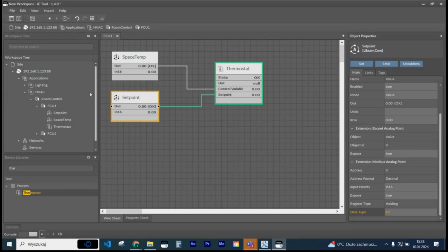The intention from day zero for Nano Edge Engine was to develop a piece of software which allows those devices to become native Modbus and BACnet. Like you mentioned, Tobias, you didn't do anything special to discover those devices over BACnet and Modbus. Out of the box, when you power up a device with Nano Edge Engine, it is already going to be available from the factory on Modbus and BACnet IP networks. And I think RS-485 as well. Yes, we're not going to show everything, but we do support exposition over RS-485. There's a little configuration needed, but still not too many steps.